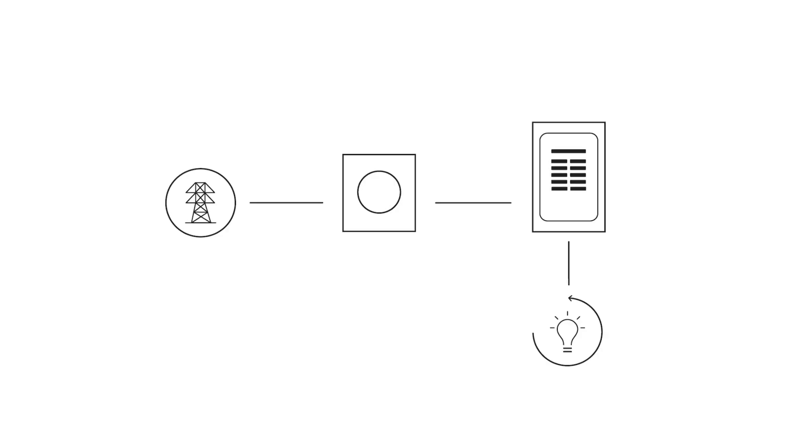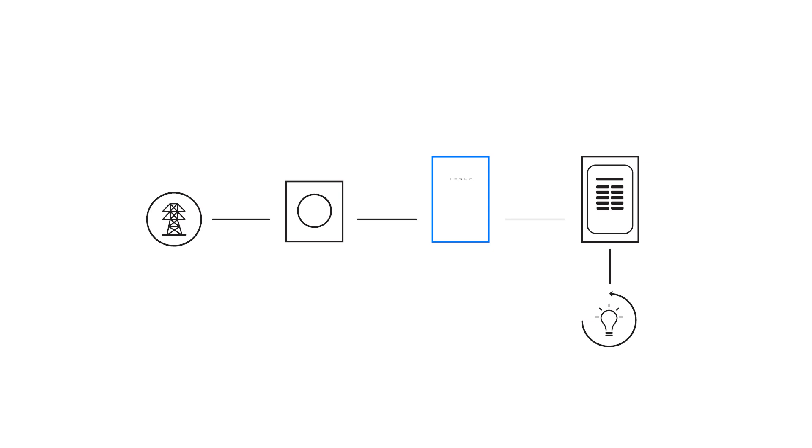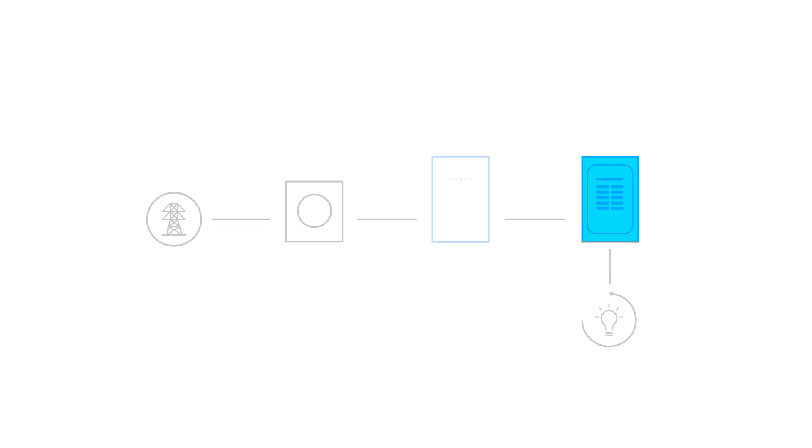This home has a standard meter that feeds a main panel. Currently, power flows from the utility meter into the home's main electrical panel. Installers will mount Gateway near the existing electrical service and intercept the feeders coming from the utility meter, redirecting them to the supply terminals in Gateway. Then, wiring connects the Gateway backup terminals to the electrical panel that contains all the home loads.